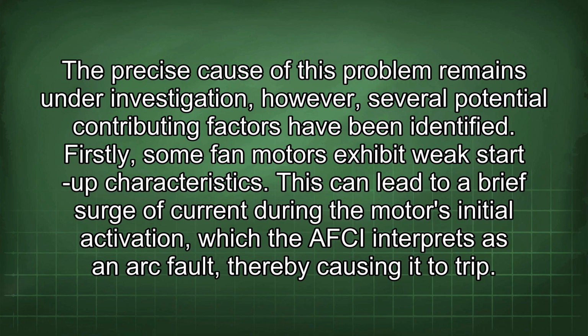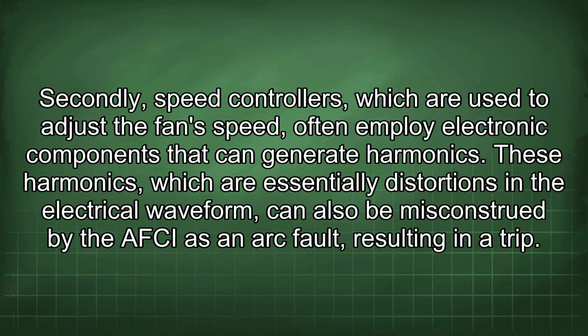Firstly, some fan motors exhibit weak startup characteristics. This can lead to a brief surge of current during the motor's initial activation, which the AFCI interprets as an arc fault, thereby causing it to trip. Secondly, speed controllers, which are used to adjust the fan's speed, often employ electronic components that can generate harmonics. These harmonics, which are essentially distortions in the electrical waveform, can also be misconstrued by the AFCI as an arc fault, resulting in a trip.